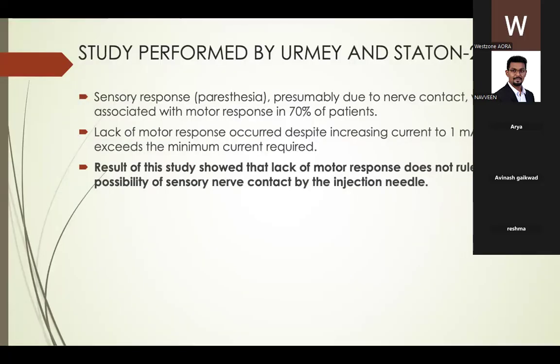There was a study performed by Urmey and Staton in 2002. He stated that a sensory response, which is paresthesia, presumably due to nerve contact, was not associated with motor response in 70% of the patients. What he's trying to say is there was a lack of motor response despite the current being 1 milliampere, which exceeded the minimum current required to stimulate a nerve. This result showed that the lack of motor response does not rule out sensory nerve contact by the injection needle, because the pulse width we have set, 0.1 millisecond, stimulates only the motor fibers, not the sensory. So we have to be careful of this.